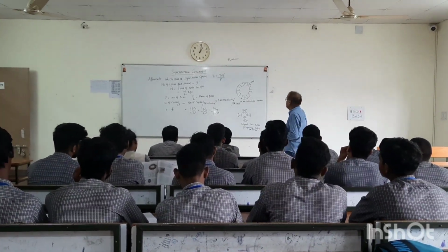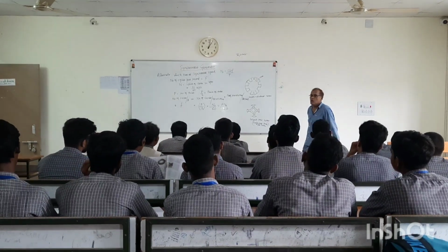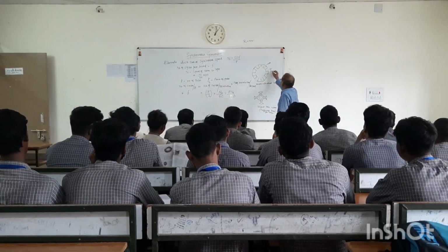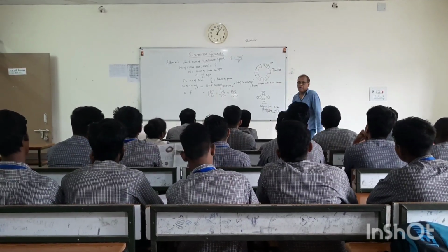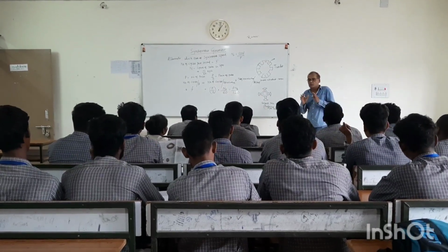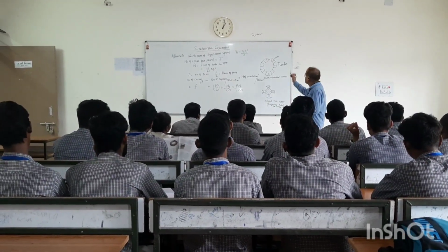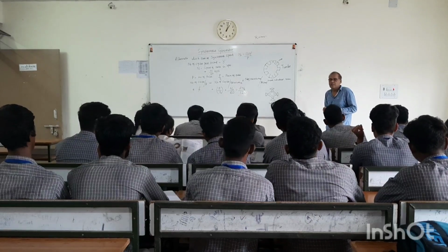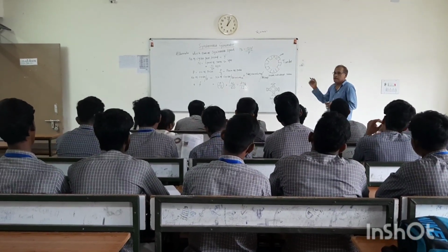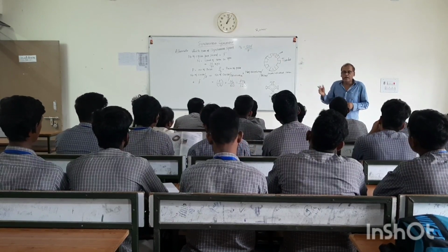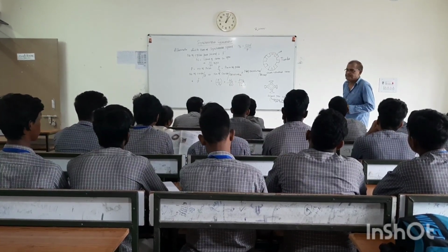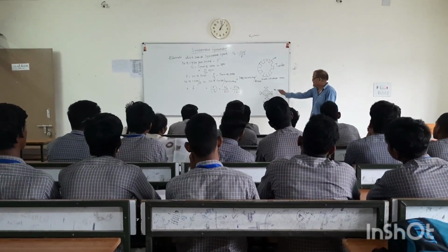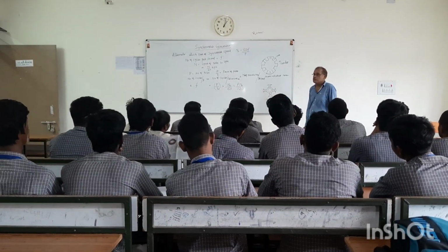From this figure, a smooth cylindrical rotor is used with a steam turbine, and that is called a turbo alternator. Whereas in this figure, that is called a salient pole rotor, which is invariably used in hydroelectric power plant based turbines. Here, for example, there are four poles, arranged north pole to south pole, again north pole and south pole.